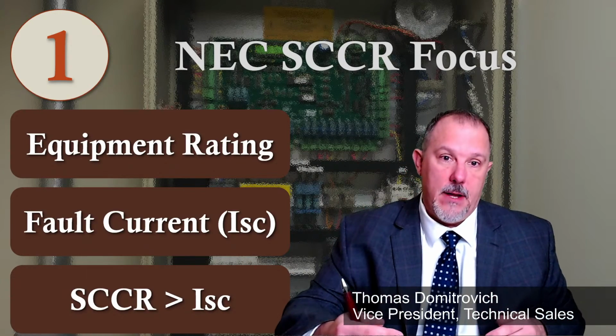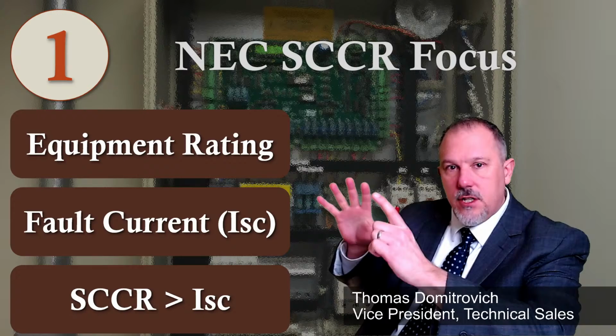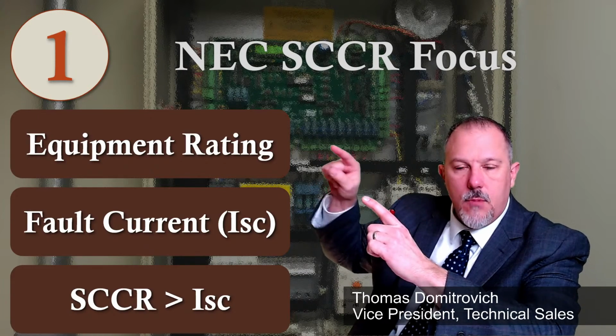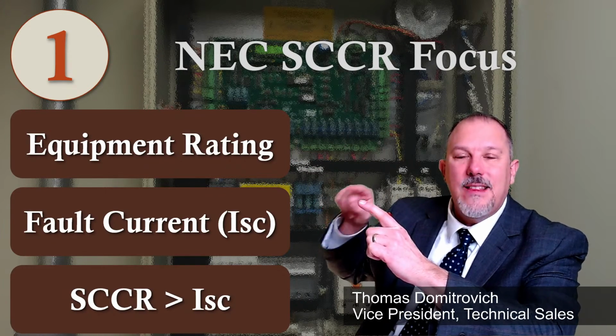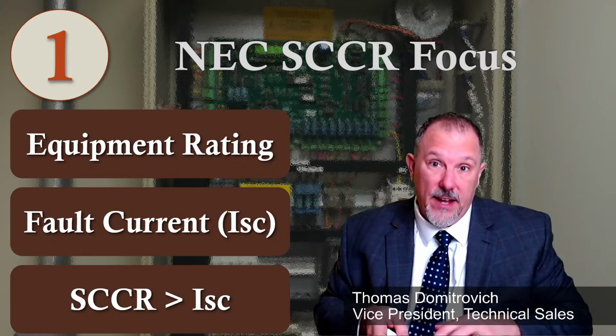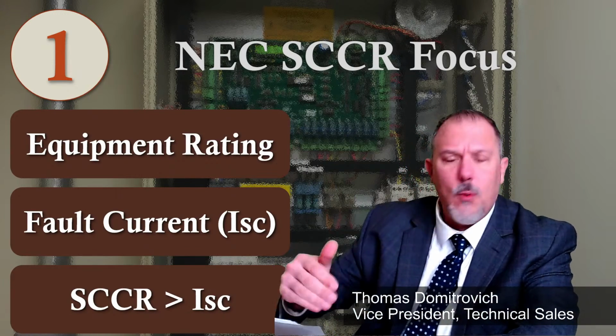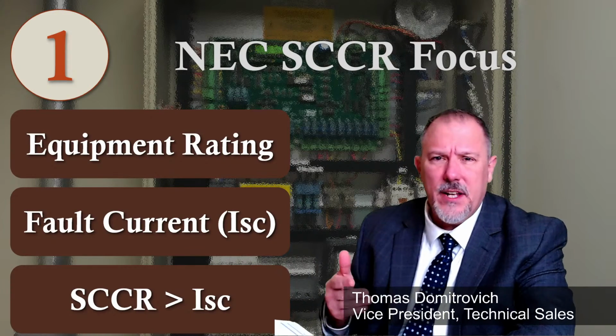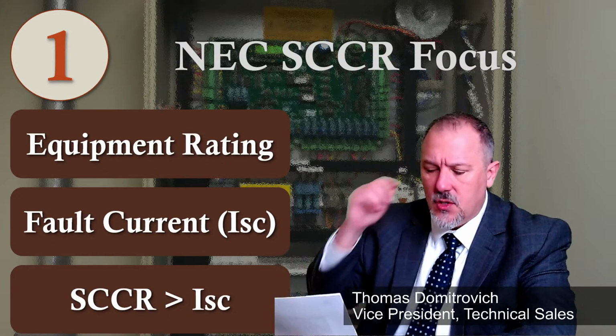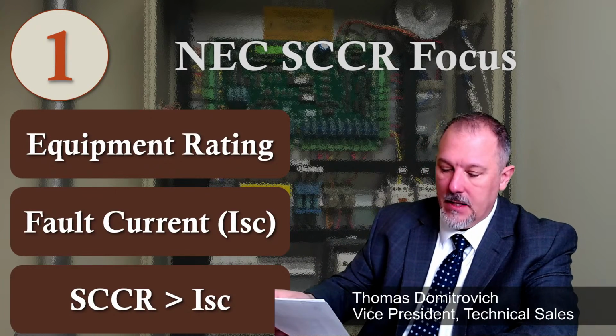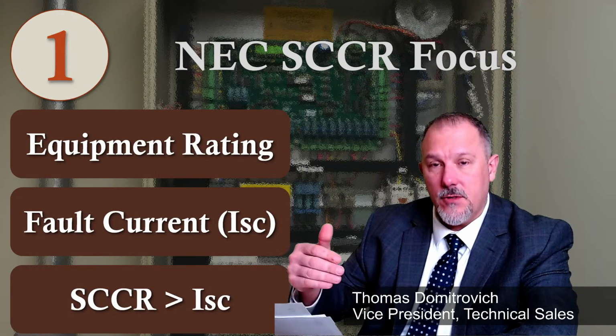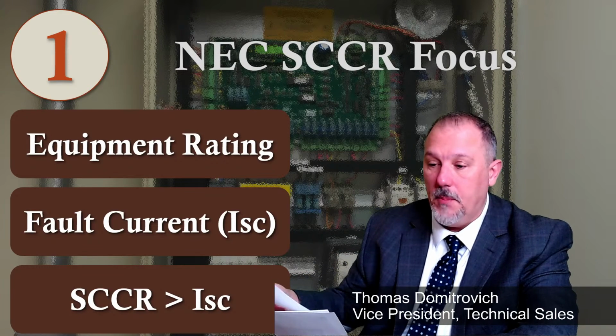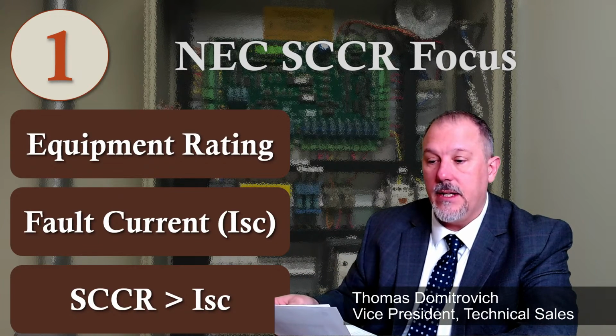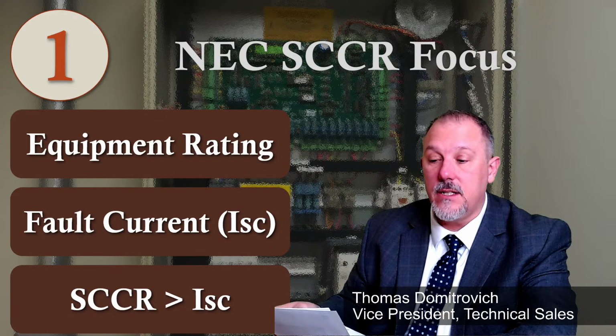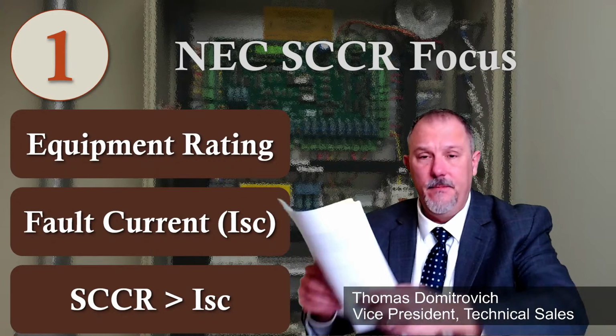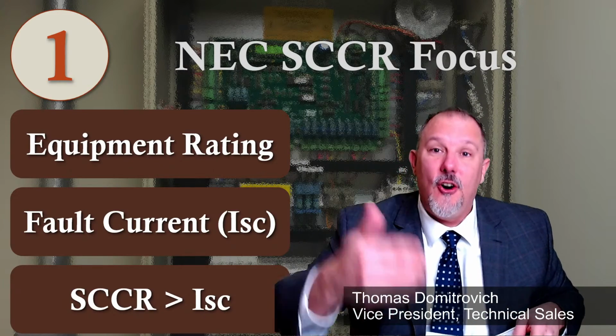And here's where the problem lies. We have the National Electrical Code making changes in these areas. They're raising the awareness. They're saying, look, you need to mark the equipment rating. You need to mark the available fault current, for example, on elevator control panels. There's a requirement now in the 2020 code. I'd have to double check, but I think it was the 2020 code. That's the code that I took all of this out of. There's a marking requirement for available fault current on the elevator control panels, and that would be found in Article 620, Section 620.51(D)(2). That requires you to mark the available fault current on the elevator control panel.